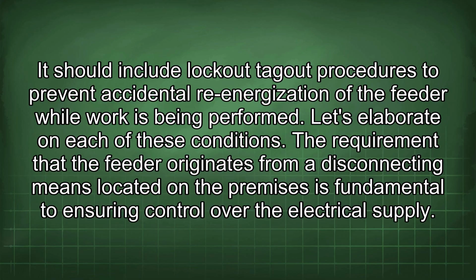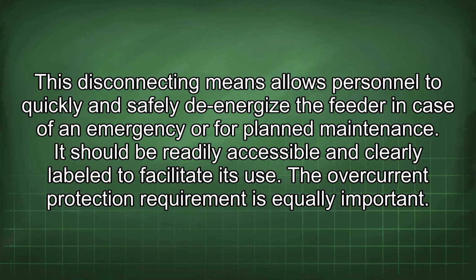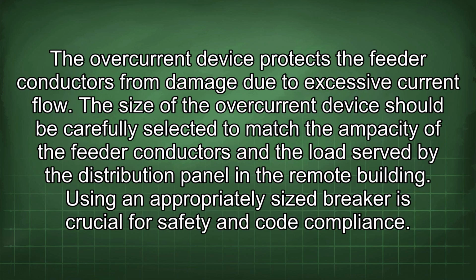The requirement that the feeder originates from a disconnecting means located on the premises is fundamental to ensuring control over the electrical supply. This disconnecting means allows personnel to quickly and safely de-energize the feeder in case of an emergency or for planned maintenance. It should be readily accessible and clearly labeled to facilitate its use. The overcurrent protection requirement is equally important. The overcurrent device protects the feeder conductors from damage due to excessive current flow. The size of the overcurrent device should be carefully selected to match the ampacity of the feeder conductors and the load served by the distribution panel in the remote building. Using an appropriately sized breaker is crucial for safety and code compliance.